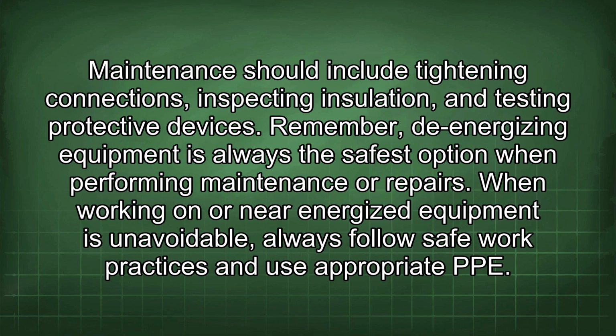Maintenance should include tightening connections, inspecting insulation, and testing protective devices. Remember, de-energizing equipment is always the safest option when performing maintenance or repairs. When working on or near energized equipment is unavoidable, always follow safe work practices and use appropriate PPE.